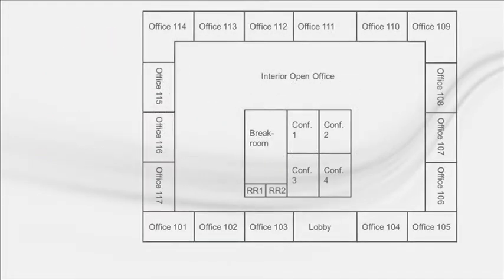Let's look at an example office building that will use a VRF system. This building is too large for a single VRF system to handle it, so we'll need to divide the building into zones that match outdoor unit capacity. If we zone this building to use heat pump VRF systems, the zones connected to the outdoor unit must have common heating and cooling needs. If not, the zones that require cooling will be uncomfortable during the time the outdoor unit is attempting to satisfy the zones that require heating, and vice versa.